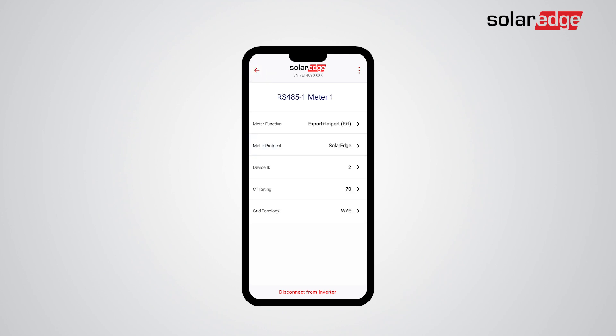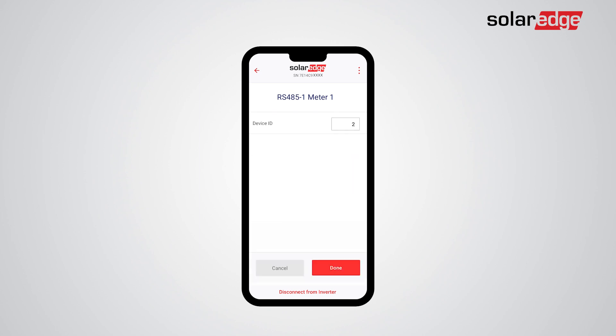Tap Back, then choose Device ID. In order to configure the Modbus ID of the meter you will need to enter the device ID number. The default device ID is 2. Make sure the meter settings match the device ID entered in this screen.